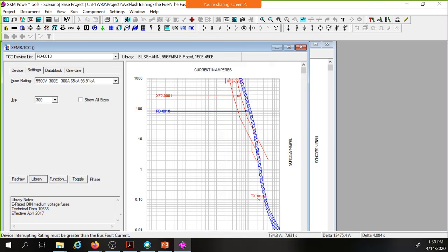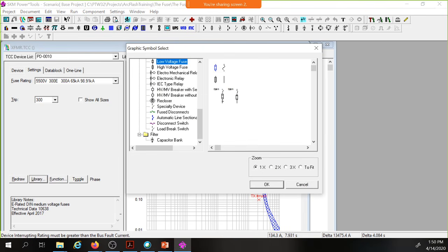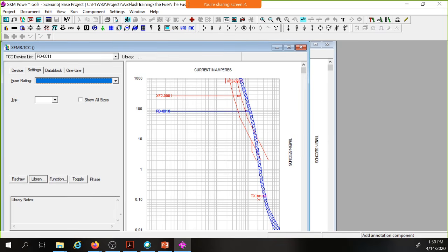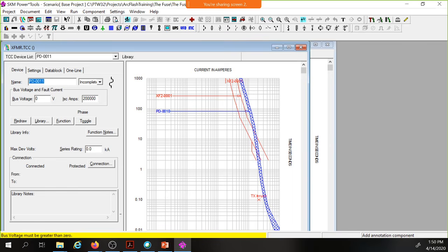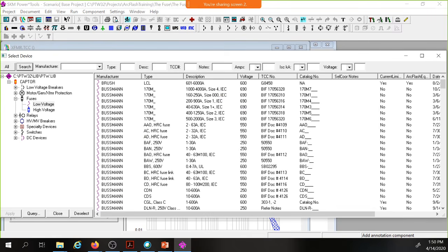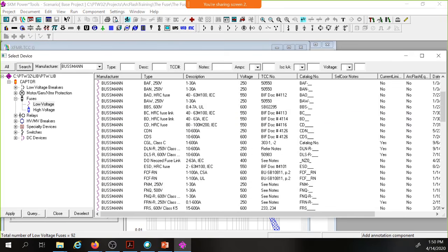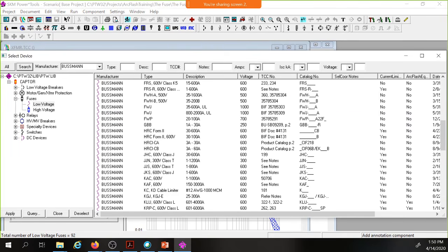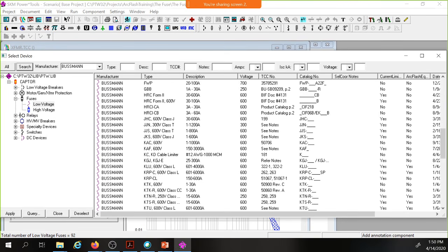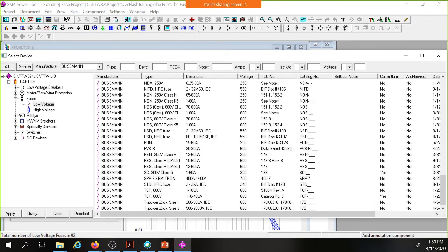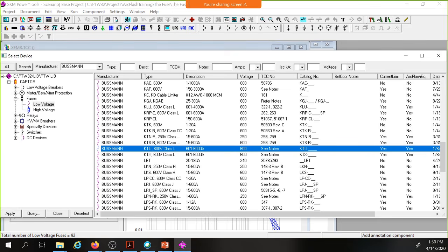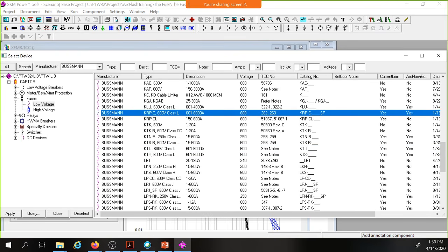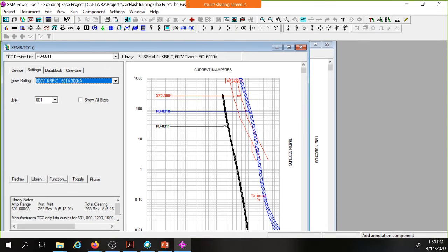So if I looked at the secondary, let's add a secondary low voltage fuse. I would probably have a Class L fuse there, so we're going to give it a voltage rating of 480. I'm doing this on the fly; I'm not building a one-line diagram and all that. I'm going to pick a Class L fuse around 1800 amps or so. Here we go: there are my KTUs, KRPs, KRPCs. So let's say I picked an 1800 amp fuse. This is on the secondary.